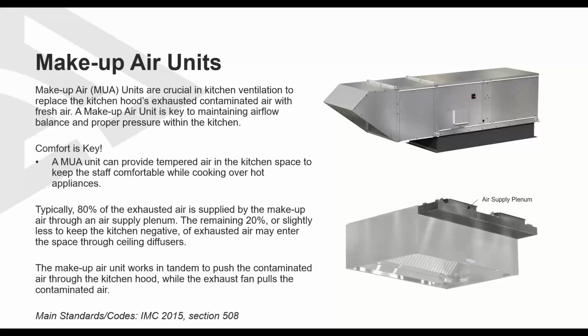Makeup air units are crucial in our KVS systems to replace the kitchen hood's exhausted contaminated air with fresh air. A makeup air unit is key to maintaining airflow balance and proper pressure within the kitchen. With makeup air units, you want to think about comfort. These units can provide tempered air in the kitchen space to keep the staff comfortable while cooking over hot appliances. Typically, 80% of the exhausted air is supplied by a makeup air unit through the air supply plenum of the kitchen hood, which you can see in this image right here. The remaining 20% or slightly less to keep the kitchen negative of the exhausted air may enter through the ceiling diffusers.